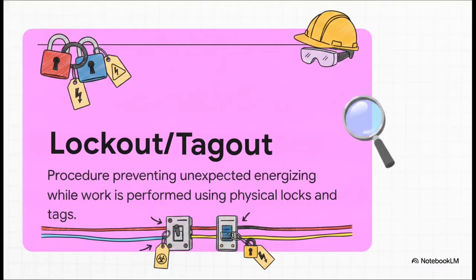This is lockout/tagout, often referred to as LOTO. It's the ultimate procedure where an authorized worker uses personal locks to physically prevent anyone from restoring power while they work on a system. It ensures that the equipment remains completely de-energized. The lock provides the physical restraint, ensuring a switch or breaker cannot be moved, while the tag identifies exactly who applied the lock and warns everyone else not to touch it. Every authorized worker on a job applies their own personal lock, meaning the machine cannot be turned back on until every single worker is finished and safe.